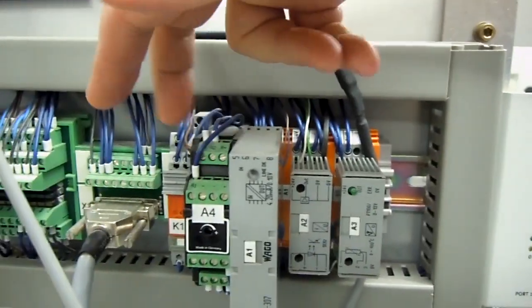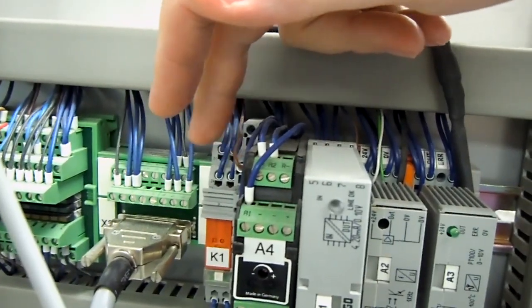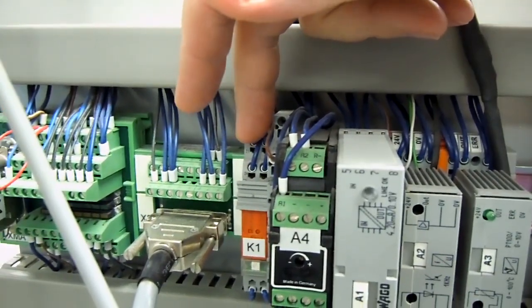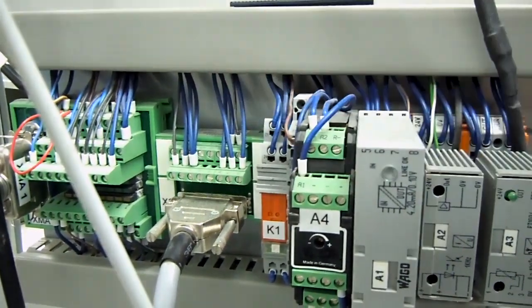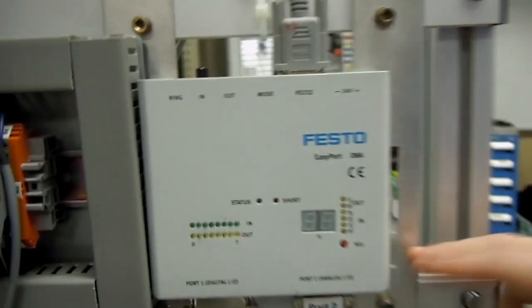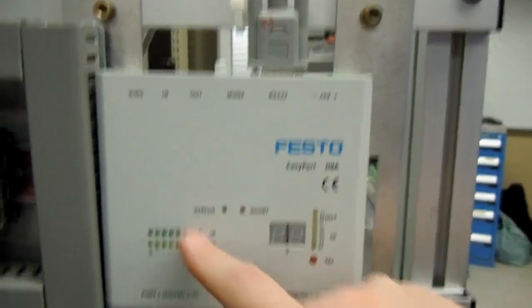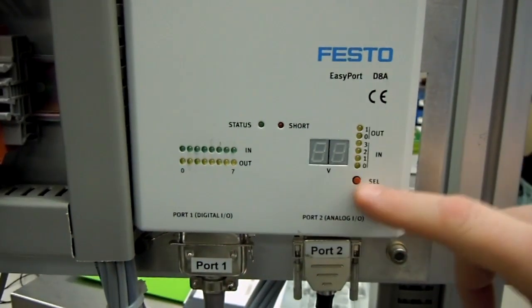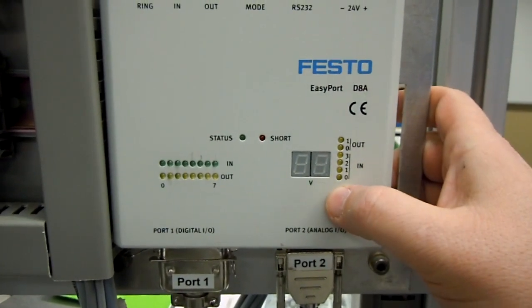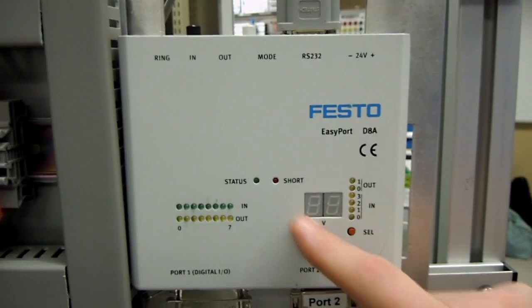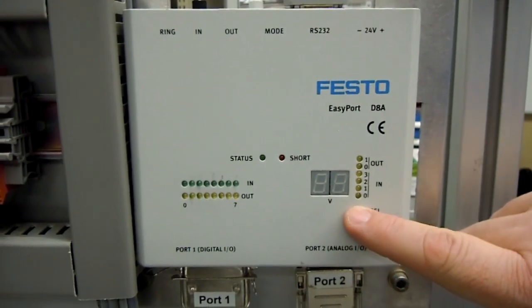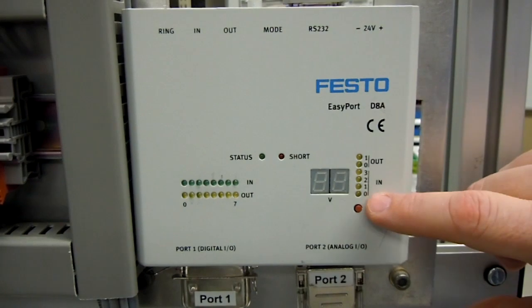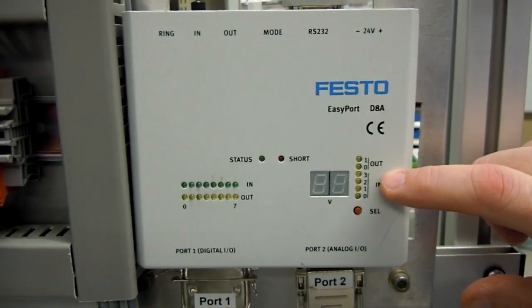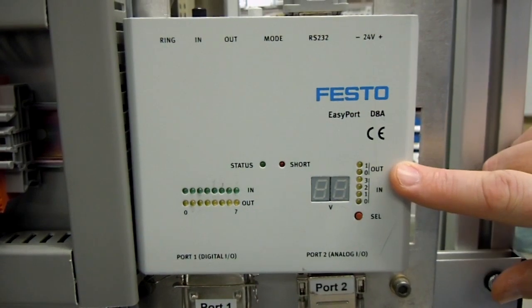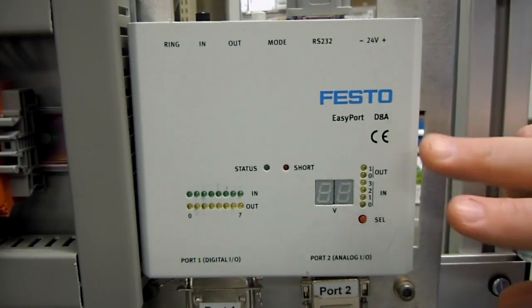This is the motor controller. Over here are two other ones that are not measuring, but they're relays for the solenoid valve and for the motor controller. So those are two relays that will come on and off. Over here is a box that we're going to use to monitor the inputs, the outputs, and the analog signals, and to switch between analog channels, you press this red button and it'll show you the voltage from 0 to 10 for the 4 analog inputs, the level, the flow, the pressure, the temperature, and the 2 analog outputs are the proportional valve and the motor speed.